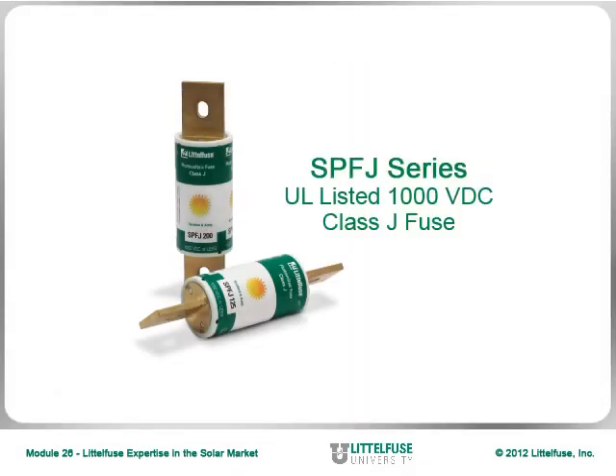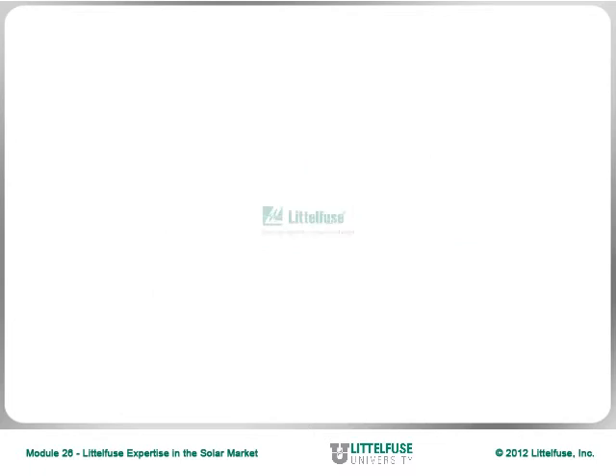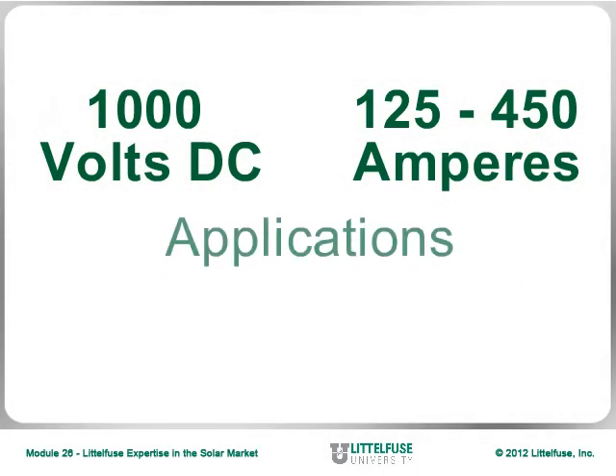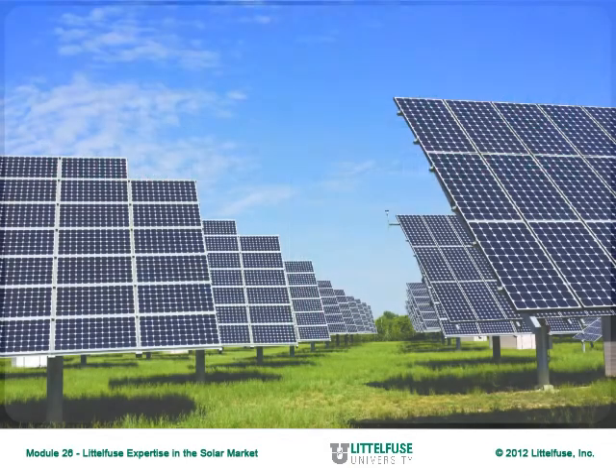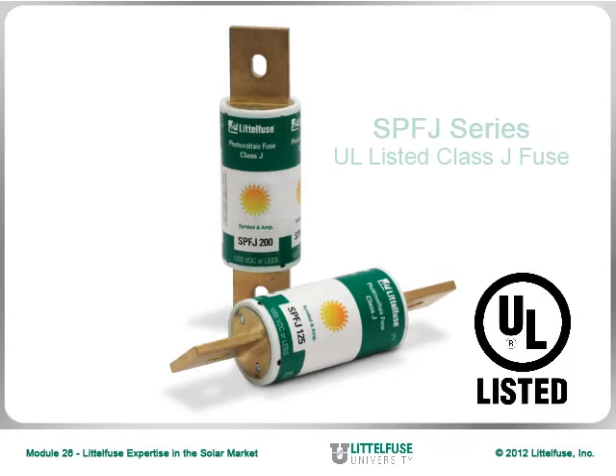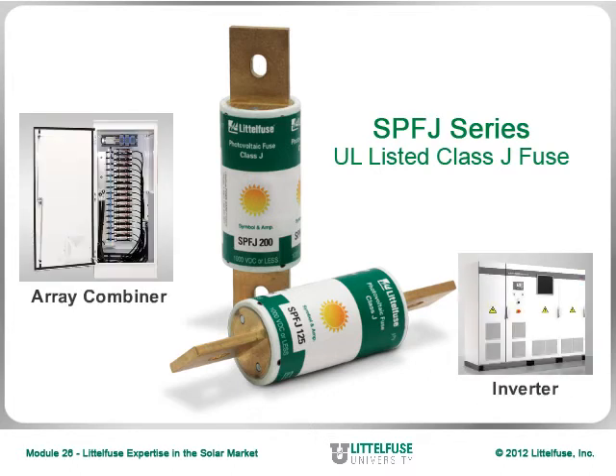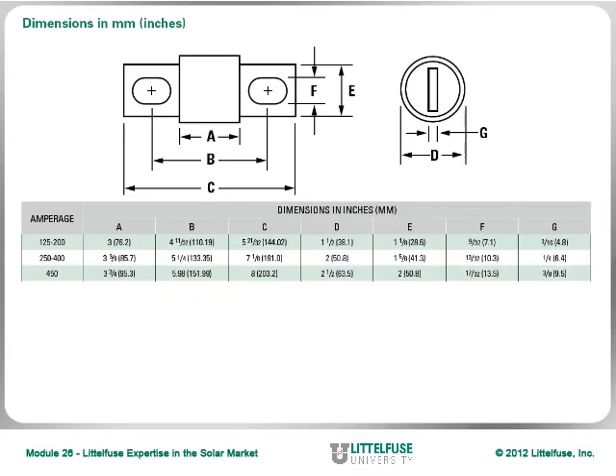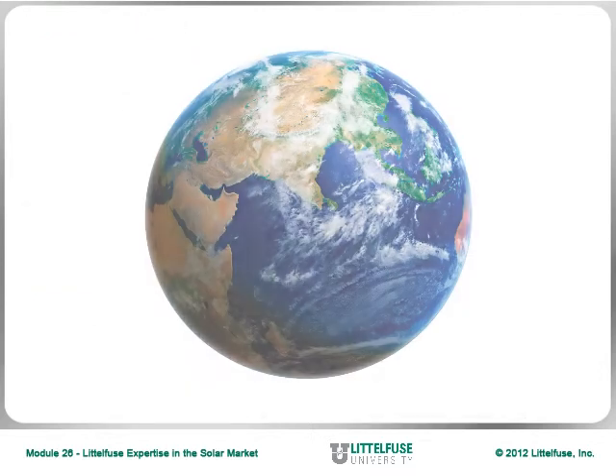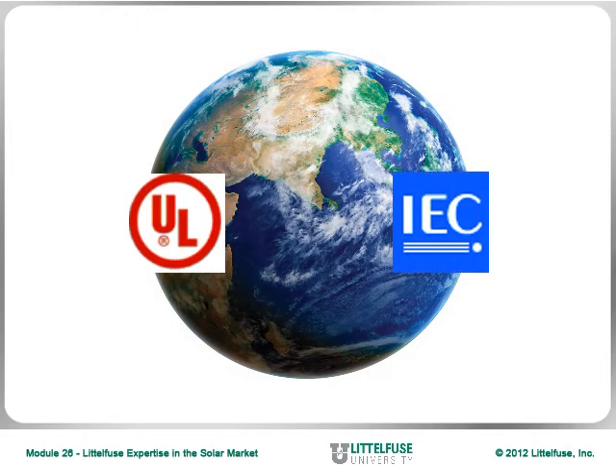We'll now shift gears and discuss the first of the two solar-related fuse series featured in this module: the SPFJ Class J Solar Fuse. New from Littelfuse, these are 1000V DC fuses for 125 to 450A applications, specifically designed for the ever-increasing voltage demands of worldwide solar applications. The SPFJ Solar Fuse is a UL-listed Class J fuse designed for higher power photovoltaic applications, such as recombiner or array combiner boxes and inverters. The smaller footprint, Class J body dimensions, and performance characteristics of the SPFJ allow this product to be globally accepted to both UL and IEC photovoltaic requirements.